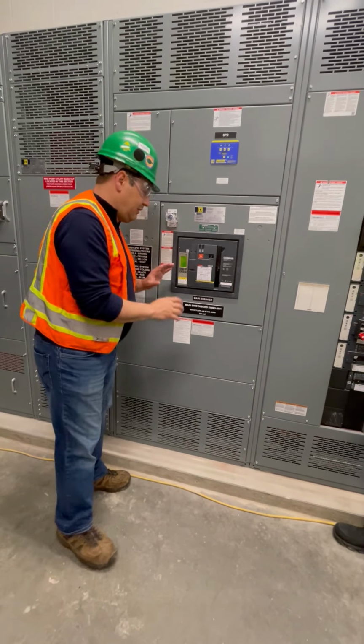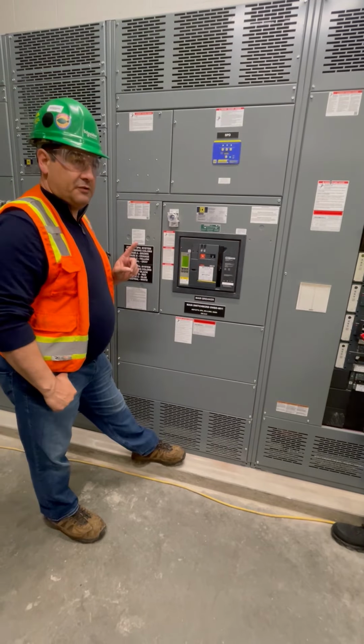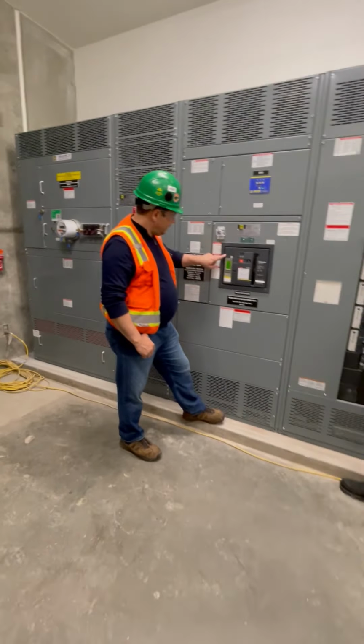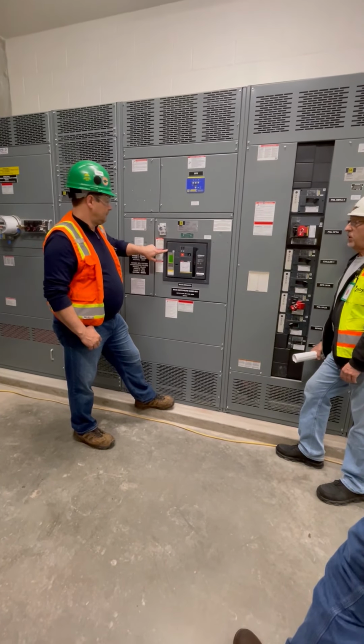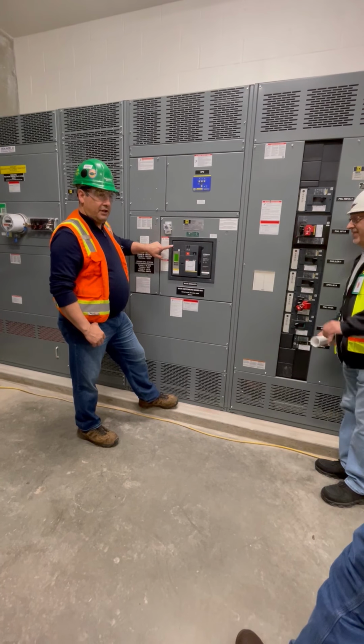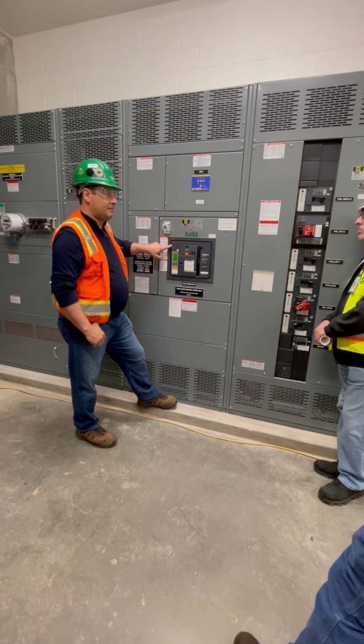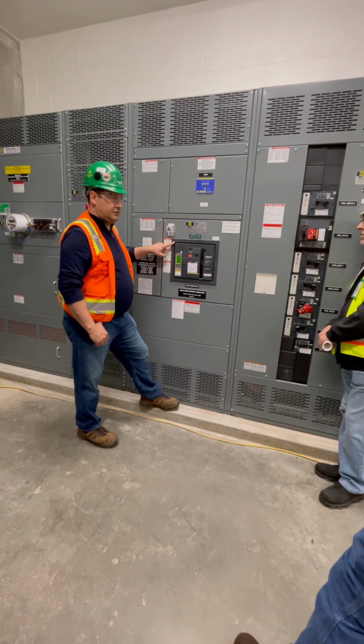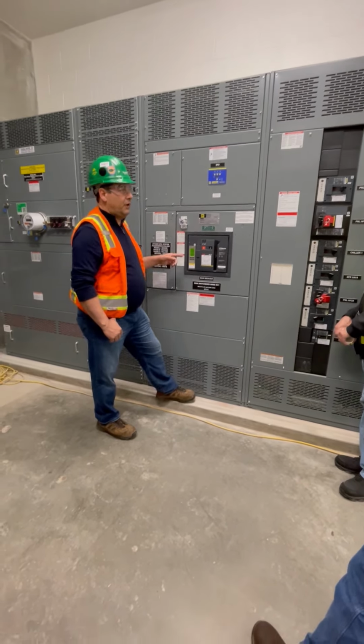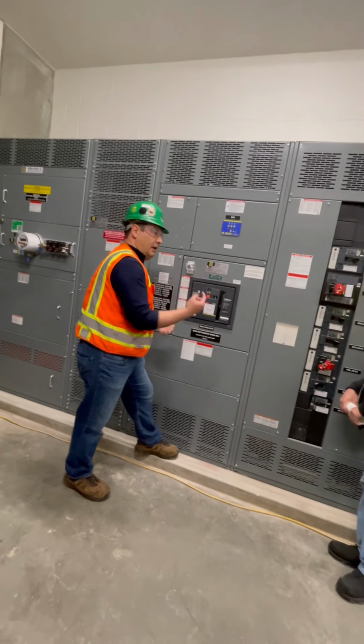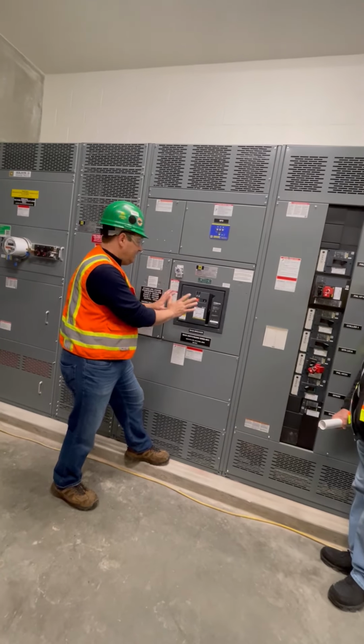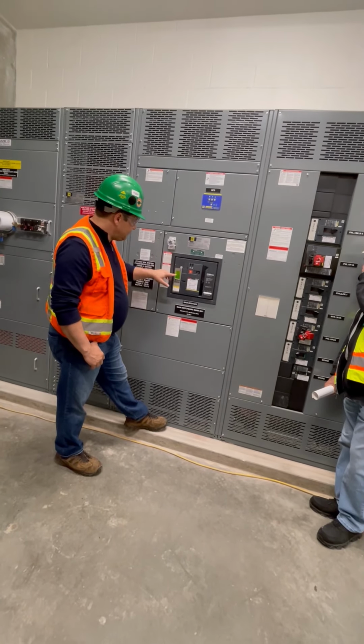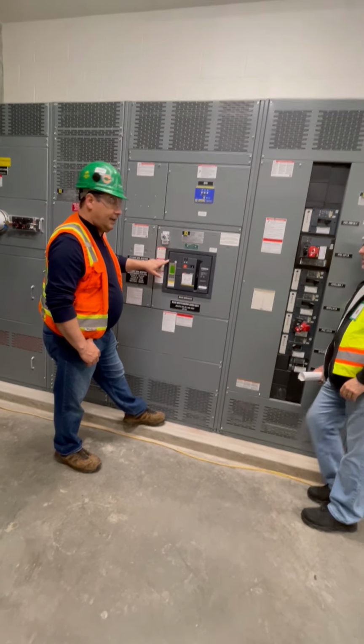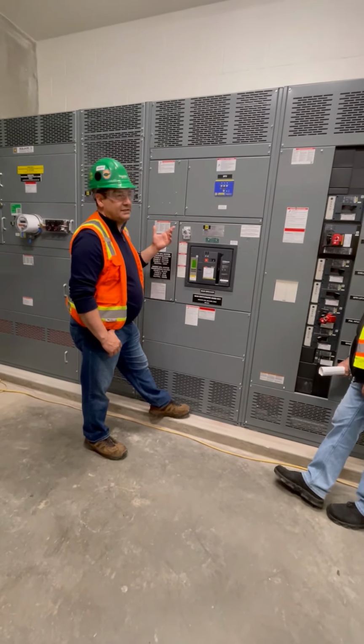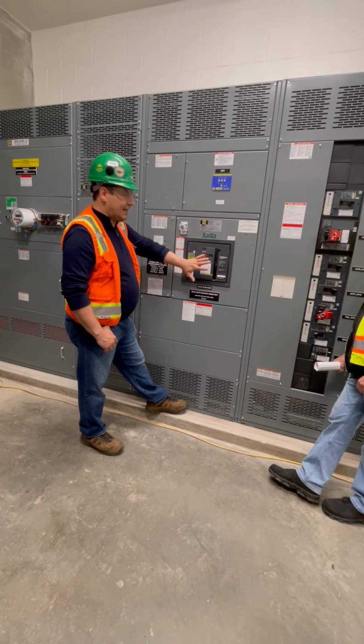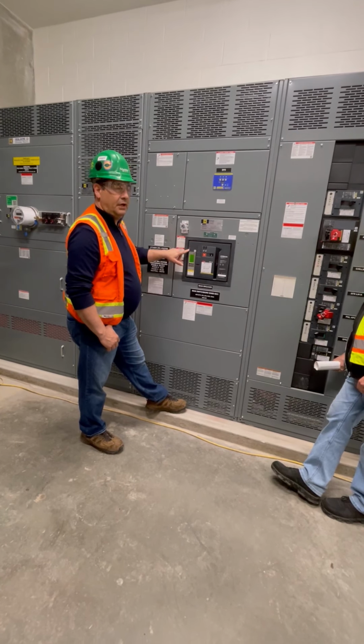Now, that's only if you want to operate that breaker mechanically, but even if it trips under fault, that button right there will pop out, like a GFI outlet. And you cannot reclose that breaker until you reset that button, okay? That's nothing but a safety feature. Because if that breaker trips under fault, it wants you to think before you rush in here and put that breaker right back on the fault. That's how these are designed, for that reason. If it trips because of a fault, it wants you to think. But again, if that's popped out, you cannot close the breaker until that's pushed back in.